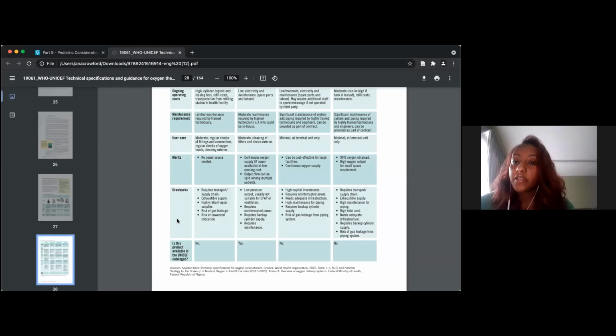But maintenance requirements: a small degree of maintenance is required for cylinders, some degree of maintenance is required for concentrators, and significant maintenance of systems and preventive maintenance is required for oxygen plants and liquid oxygen. They have high-tech requirements. So when it comes to user care for oxygen cylinders, it's about moderate: regular checks of filtering and concentration, and cleaning of the exterior is really needed. Not much else in terms of user care.